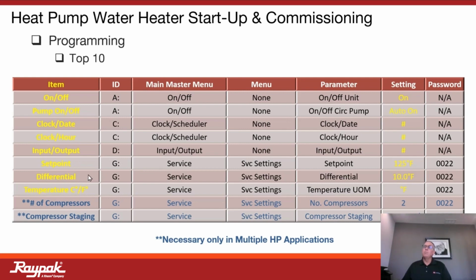The differential in a domestic water production mode, the default is 5.4 degrees. Don't ask me why. Well, I can tell you why, but let's not bog ourselves down in that minutia. But let's say I want to adjust to a 10-degree differential. So if I have 140 degree stored water temperature, when that tank falls to 130 degrees, that's going to actuate the call for heat to the individual heat pumps. So again, this is completely adjustable as well.